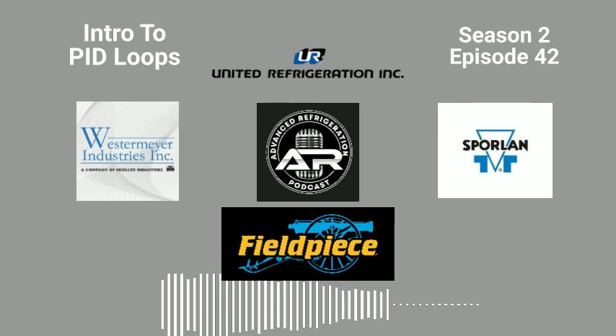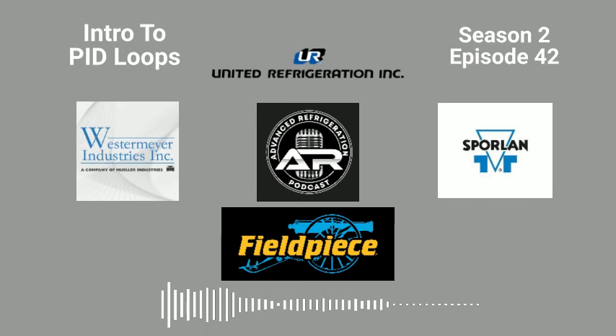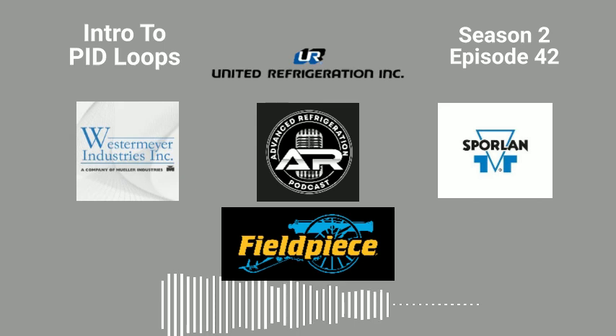Also, if you're tuning cases, make sure there's food in there. Don't tune it when there's no food in there, because it's going to change the entire load in the case. It could be more or less. I've made that mistake before. I tuned an entire store, came up with a good tune, spent 8+ hours on it, and then they loaded it up. Next day I'm there because a bunch of cases are running warm because they can't keep up.